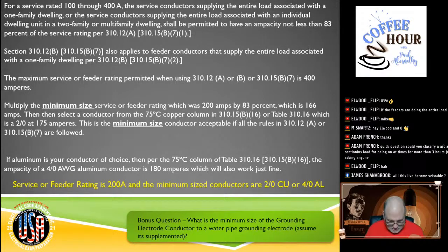Now, if you want to cheat and look at the table, go on and look at the table, which is 310.12. It has an N beside it. Now, this was previously back in informative Annex D, the table. Back earlier than that, like the 2014, I believe it was 2014, it was actually in the code. It got removed in 2017, got moved to the back. Well, people had a fit. And so, I guess, the power of the people, maybe? Would we say the power of the people? It moved it from there, and it ended up being placed back in 310.12.